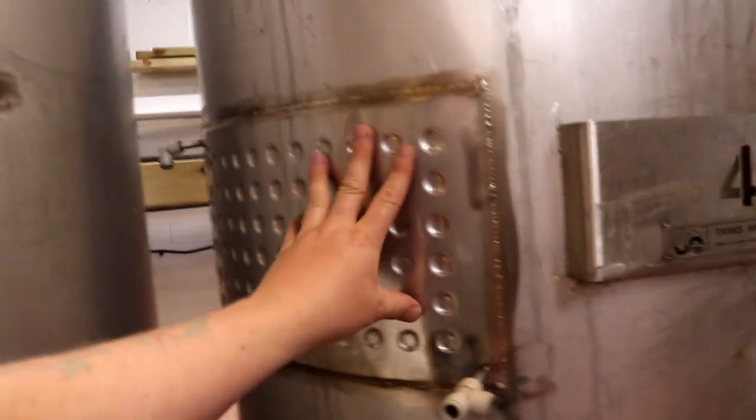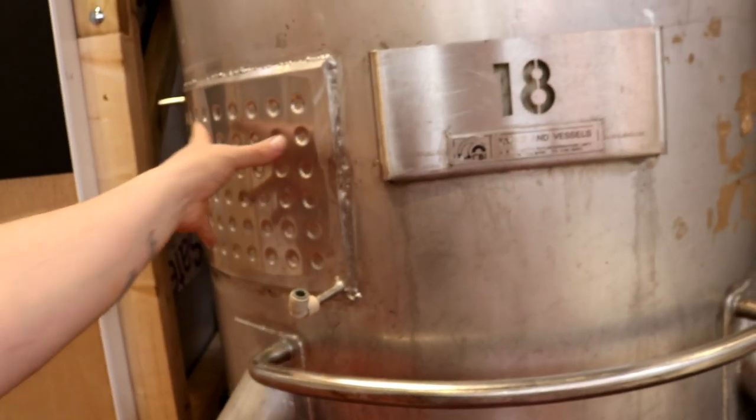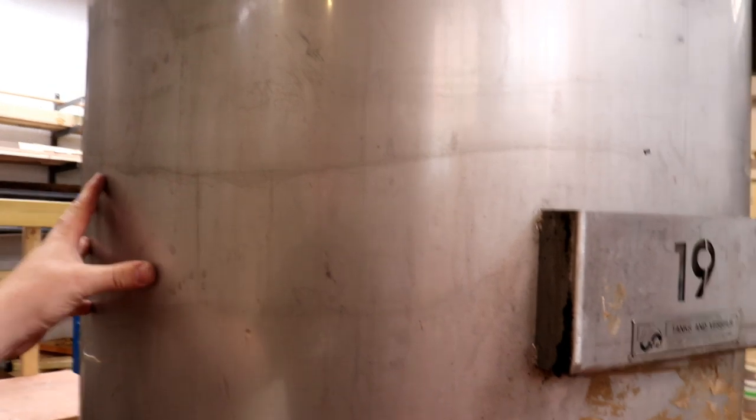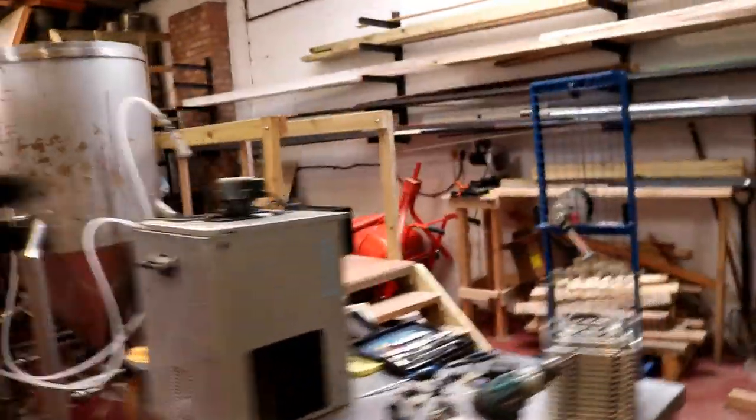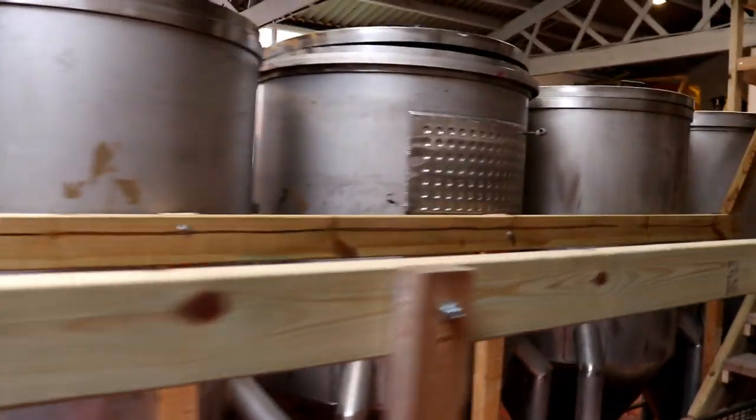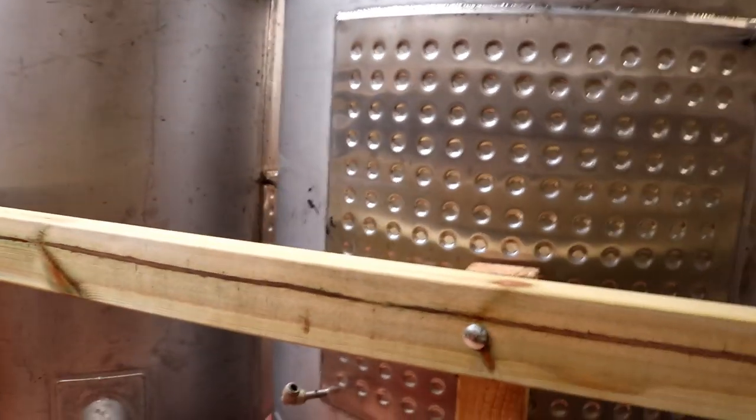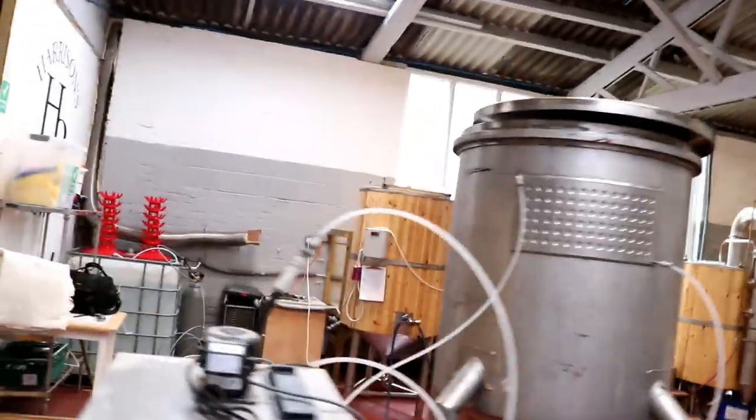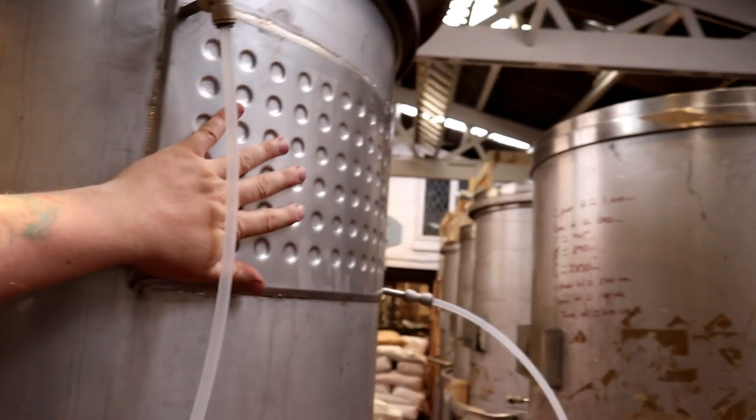So if I come across and have a look at these, they're out of the five tanks. One, two, three of them have their cooling plates at the front and on the side. And this particular tank, well if I go around the back, you'll see that this tank has got really quite a large cooling plate, bigger than all of them, but again slightly too high. But because of its dimensions that kind of compensates for where it lacks in position. So we know that this tank is no good because the glycol leaks. So we're going to highlight that mark and we're going to take this plate off at another time before we clad it, and we'll chop this off and move it.